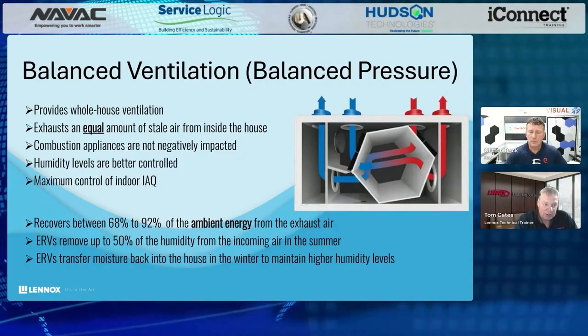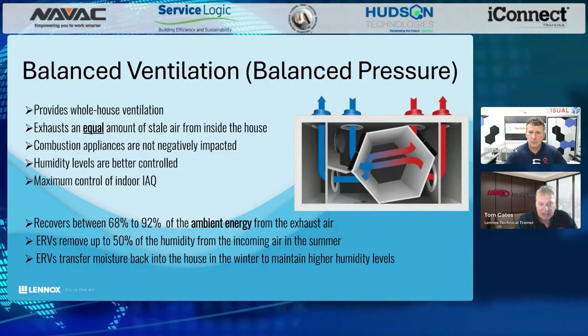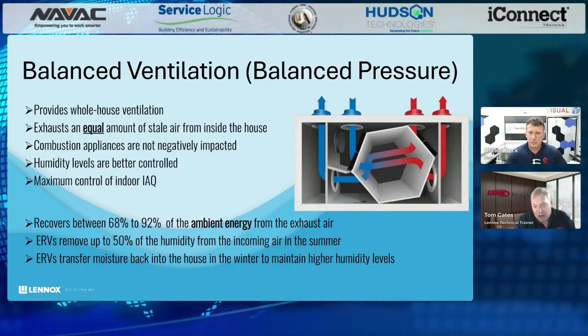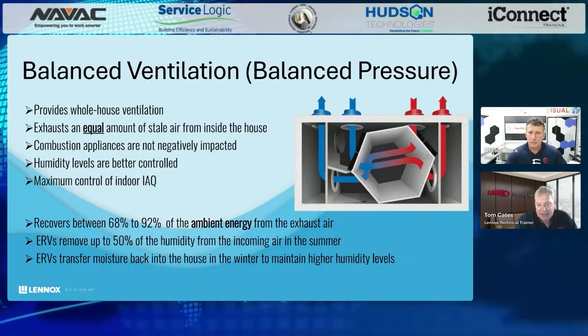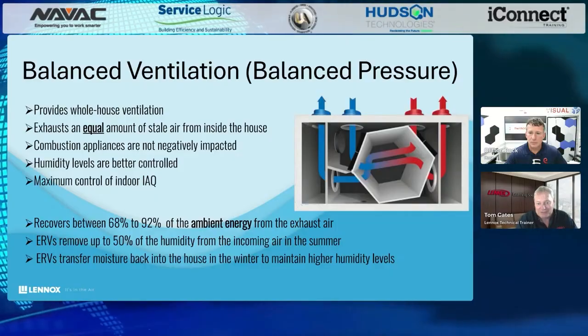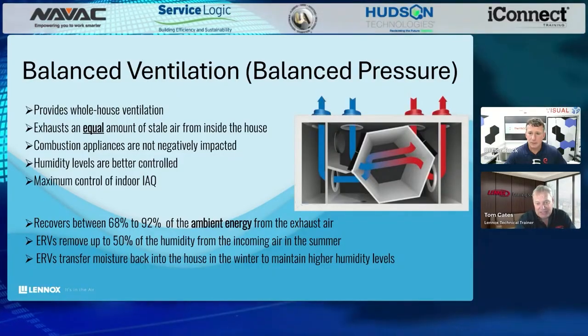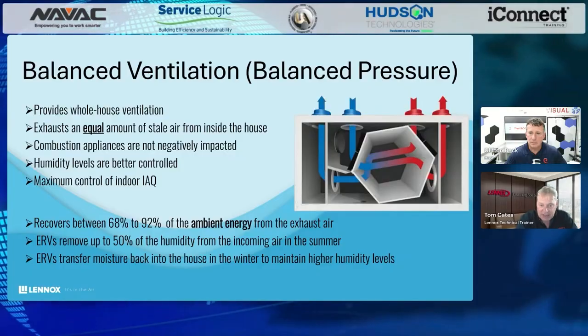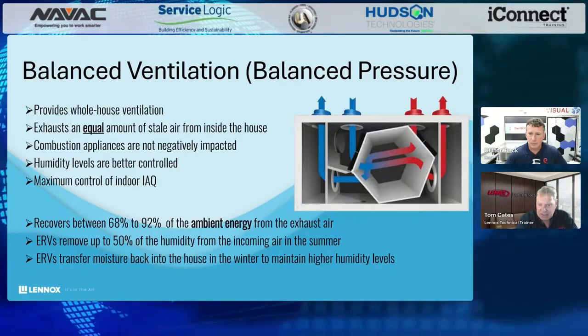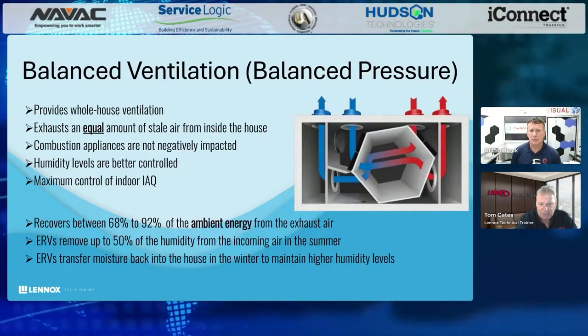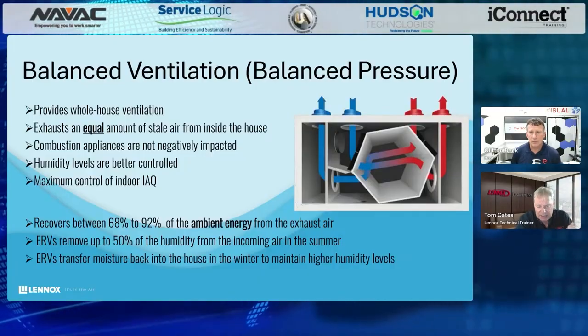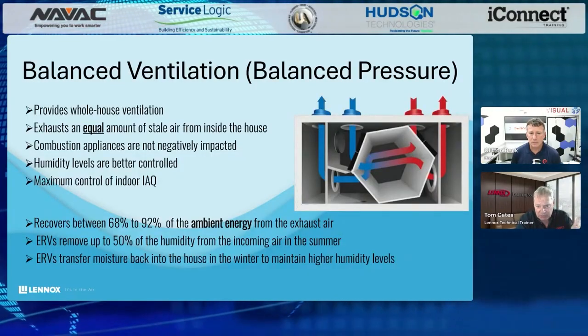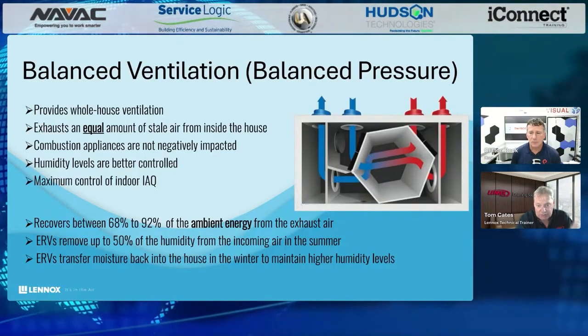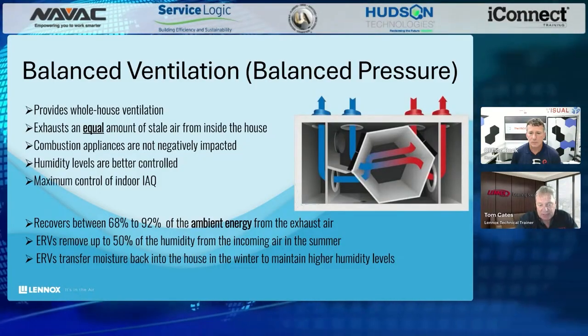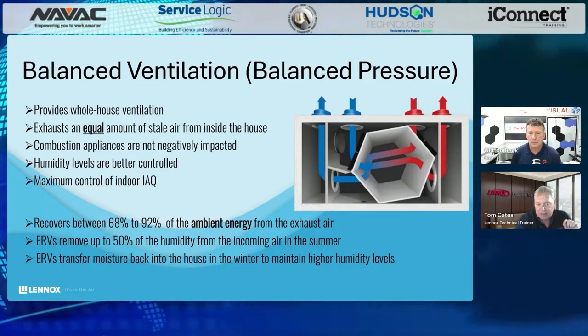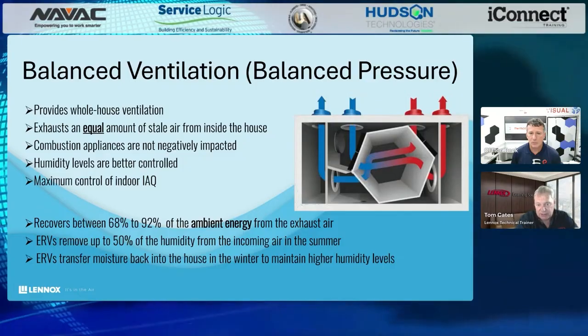Now they're building pre-manufactured plastic boxes as opposed to the metal boxes that we saw, which they can now control the cross leakage between those airstreams even better today than what we saw in the past. That's where the HRV, ERV manufacturers are working today. How do they improve the transfer capabilities of their cores? How do they improve the cross-contamination between those two airstreams? And then what kind of motor are they using?